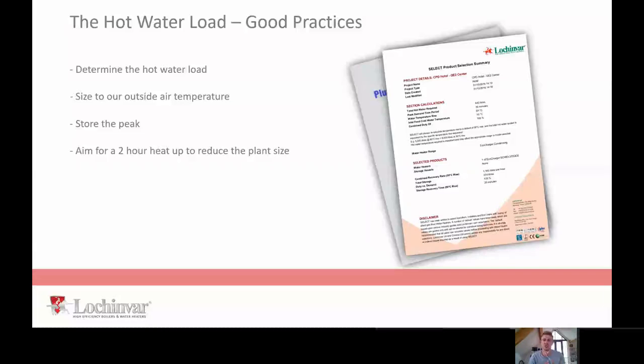And then we transitioned to what we've been working on probably for the last 5-6 years, which is a direct gas-fired water heater with 120 kilowatts of input or more, and a small storage volume, because that gets rid of our standing losses, and we can do it almost semi-instantaneously. And now we're working with heat pumps, and we're storing 10 to 20 litres per kilowatt of air source heat pump, remember? So now we're doing it with air source heat pumps. What we're doing is we're kind of doing that full loop and going back to the original idea where we store our peak and heat up over a long period of time.